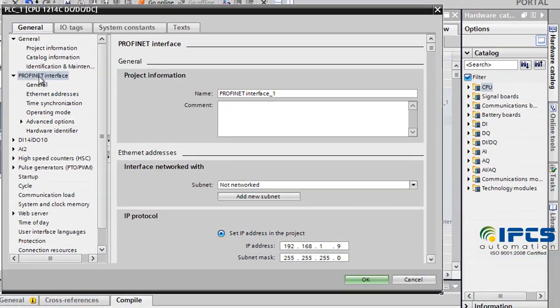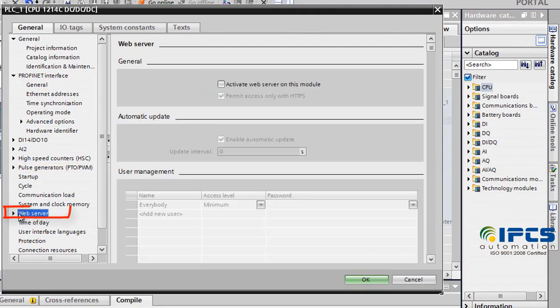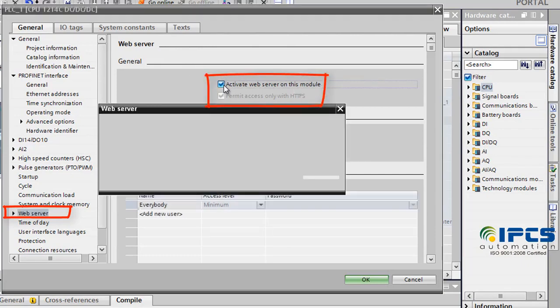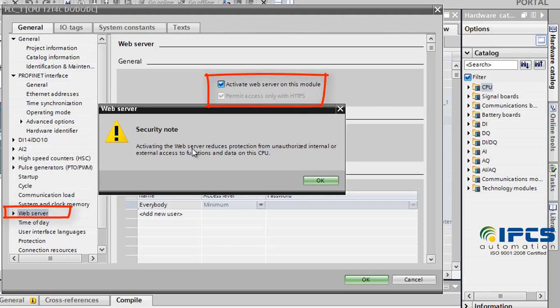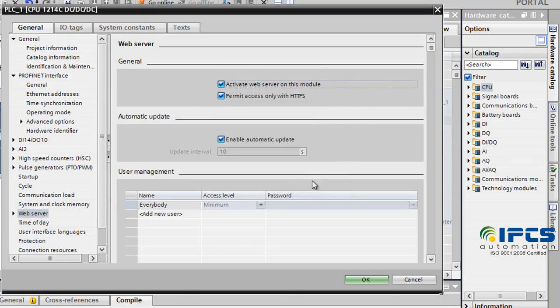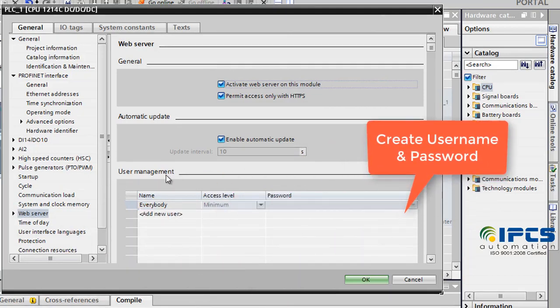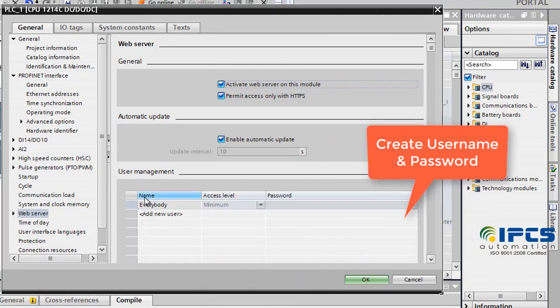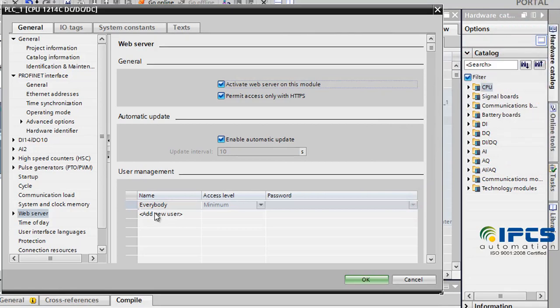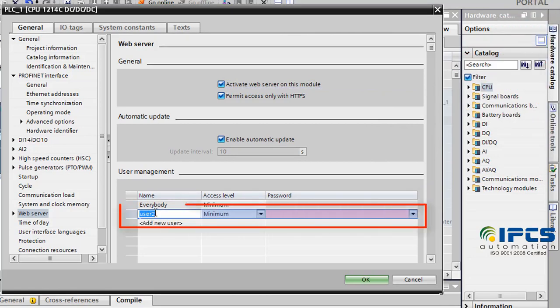In the web server settings, configure the username and password for the mobile application SIMATIC S7. Tick the checkboxes for activating the web server on the module and to permit access only with HTTPS. The username and password should be set in this box.